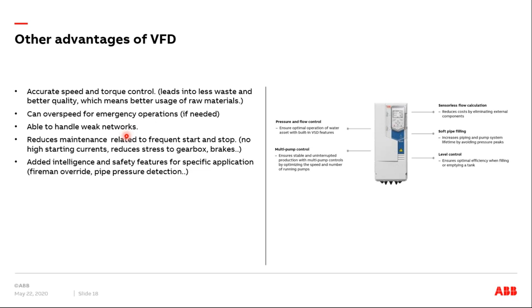The other advantage is that you can have emergency operations by overspeeding the system. For example, in an HVAC system, if you need a really high airflow for 1 hour a day, you could overspeed the system for a short time and get this emergency need fulfilled. Also, these drives are able to handle weak networks, so changes in voltages and frequencies don't affect your end applications because you have a drive interface.